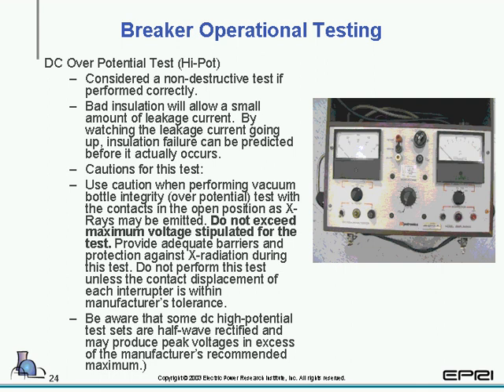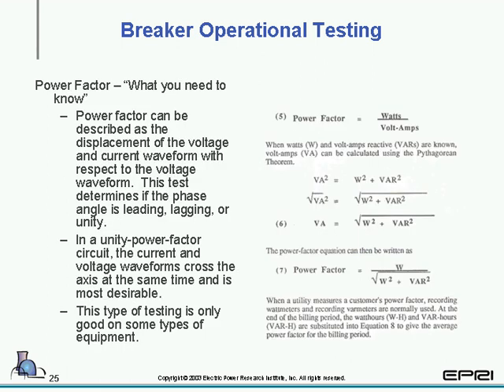The next item that you'll be looking at, or should be up on your screen, is the DC over potential testing. And again, some DC units don't actually produce DC. They produce a square wave that goes from 0 to some value, or a pulsating DC. And you must be careful because, again, do not exceed the maximum voltage, especially when checking vacuum bottles, because they can produce X-rays.